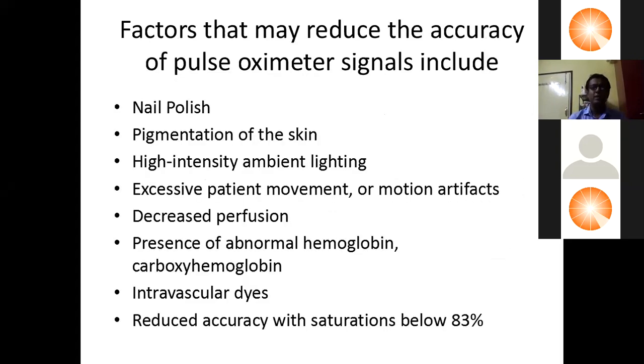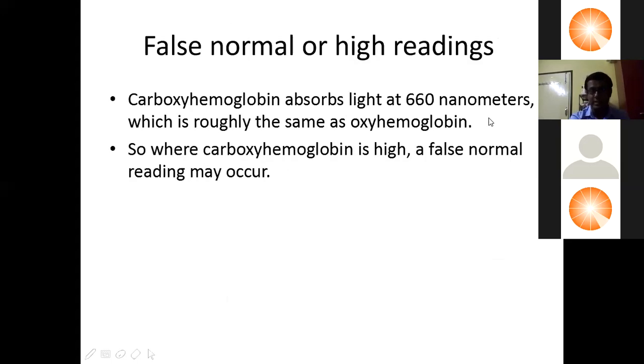Now, there are some factors that reduce the accuracy of the pulsatile signal, like nail polish, pigmentation of the skin, high intensity ambient light, excess patient movement and motion artifact, as I have mentioned, decreased perfusion, presence of abnormal hemoglobin like carboxyhemoglobin, and intravascular dyes. The accuracy of SpO2 also reduces with the fall of saturation. So at high saturation it is more accurate, and at low saturation it is less accurate.